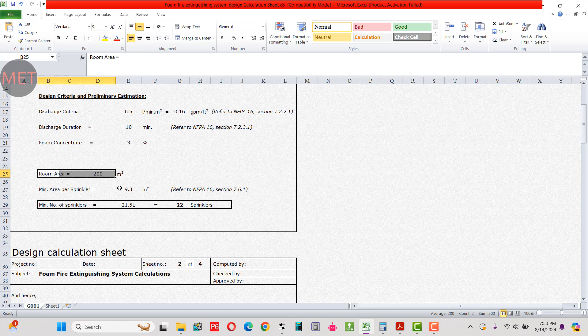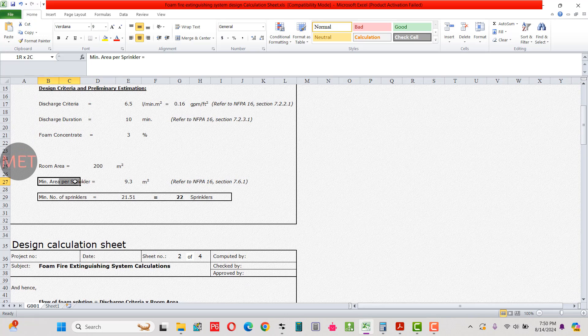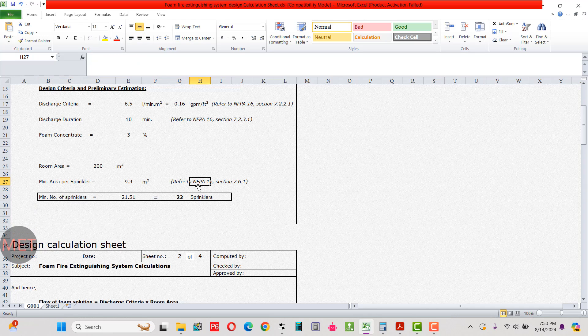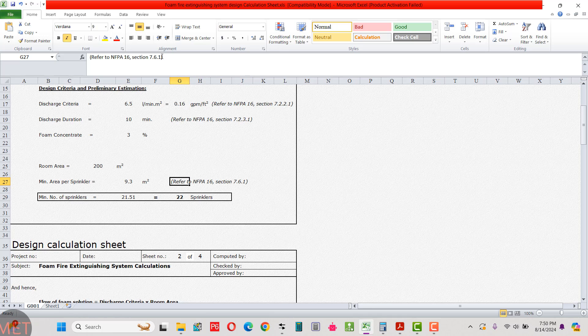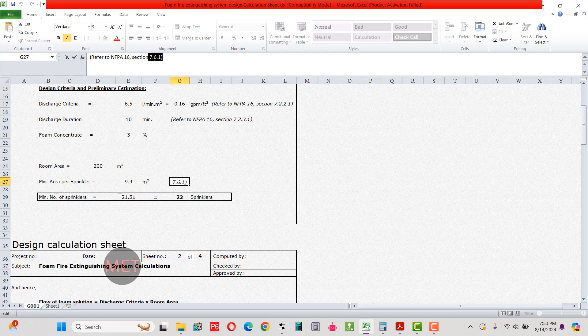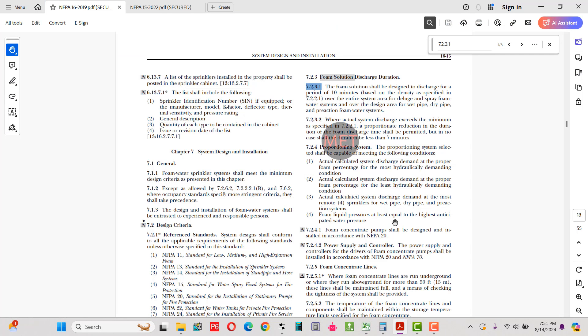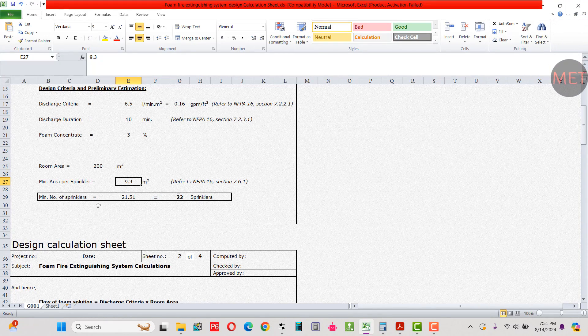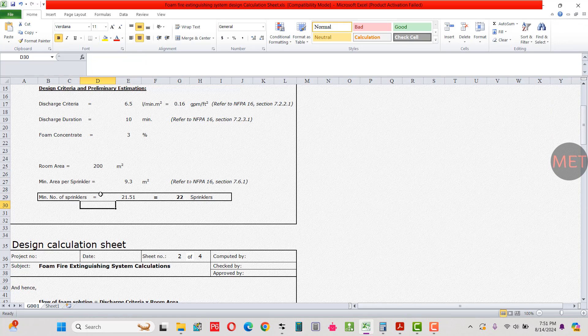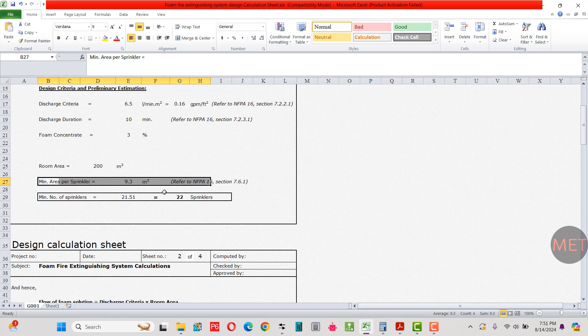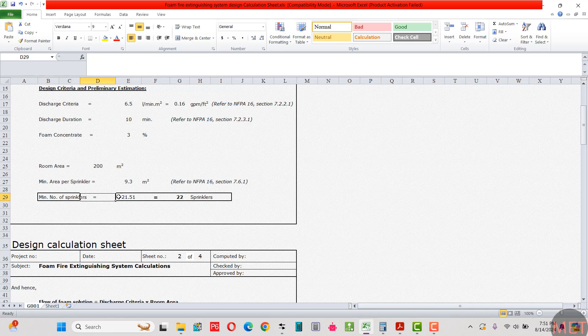The minimum area per sprinkler is 9.3 square meters as per NFPA 16 section 7.6.1. Looking at that section: sprinkler spacing shall not exceed 100 square feet or 9.3 square meters per sprinkler. So with a room area of 200 square meters divided by 9.3, we get 21.51, which rounds up to 22 sprinklers.